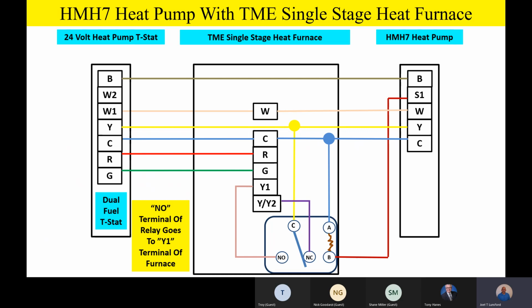And again, we're going to want 100% airflow on the normally closed contact, that Y/Y2. We want to make sure and select on the control board for our high cool on that normally closed contact. And then on the control board, we also have a spot that we can have reduced airflow for what they call low cool, and be sure and select a speed tap that's going to give you about 60% airflow on that low cool. So you'll notice that it wires just like the previous product on the air handler. It's just now we have hard terminals and they're labeled a little bit differently than we had on our air handler, but it's essentially the same thing.